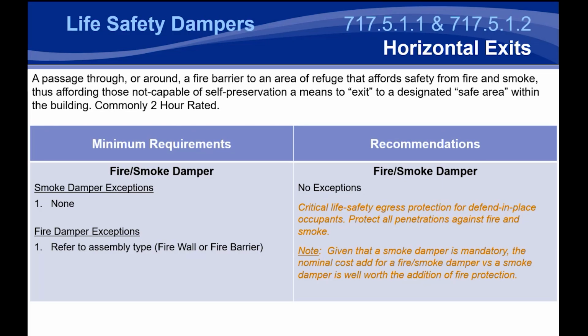One common application for this I see is in multi-story hotels. You may notice on the diagram, the floor plan, or the evacuation plan for that hotel, there may be some exits that are your closest point of egress. Now, some other exits may actually have some additional indication. So it may have a handicap symbol on that. And that handicap symbol is actually meant to designate a horizontal exit. So if there's someone that can't get up and down the stairs under their own power, they can go to that exit enclosure, that horizontal exit, and they'll have an area where they'll be safe for up to 2 hours.